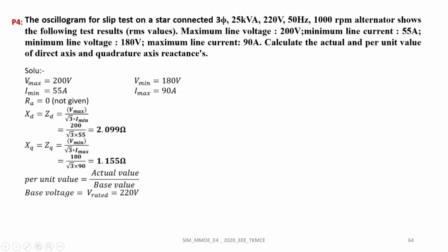So per unit value of Vmax is equal to 200 by 220 and per unit value of Vmin is equal to 180 divided by 220. Correspondingly, Vmax is obtained as 0.909 per unit and Vmin is obtained as 0.818 per unit. Now we need to calculate the base value of current using this power rating and voltage.